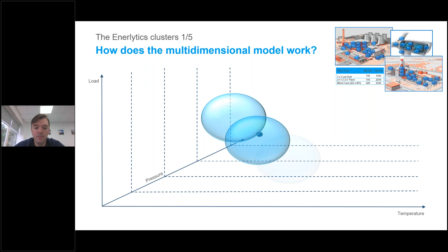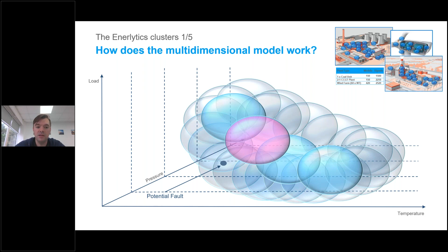Our largest models are 117 dimensions for a complex cooling water system, and then we map that across all operating modes. We put some alarming ranges in place, and then during live operation, if it moves outside one of those planned spheres, that indicates a potential fault. That's really useful because power plants produce lots of data, and no engineer can look at every piece of data every 10 minutes. So here are some case studies of that in place.